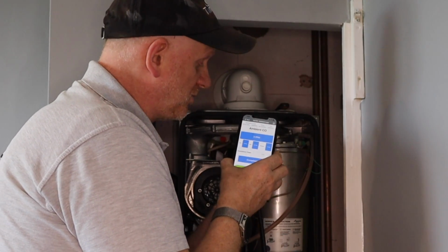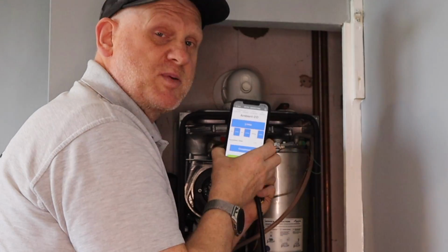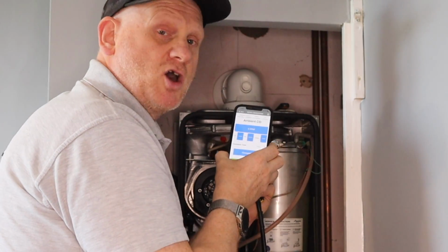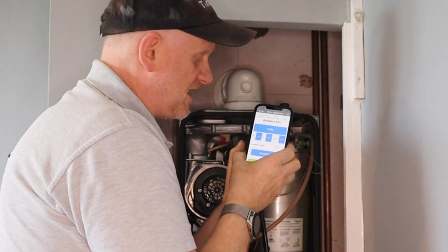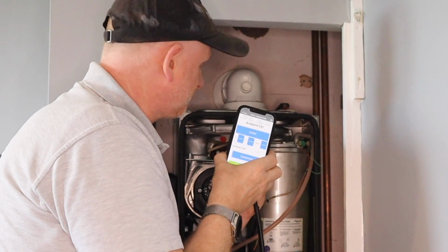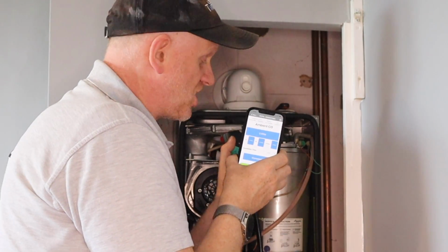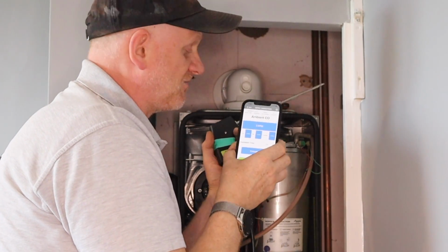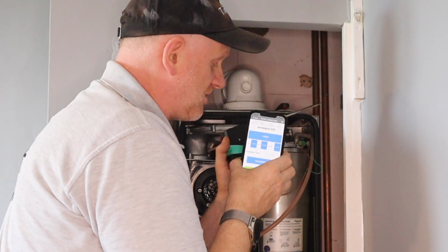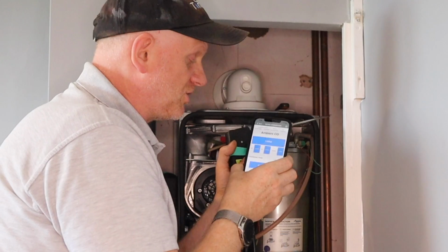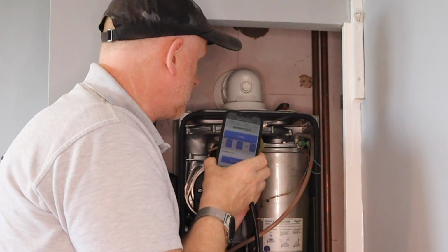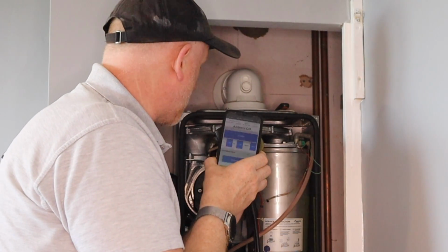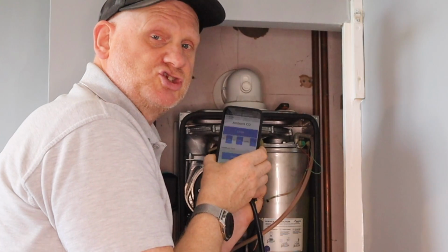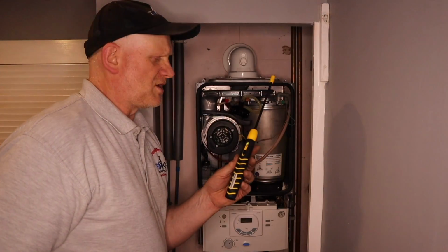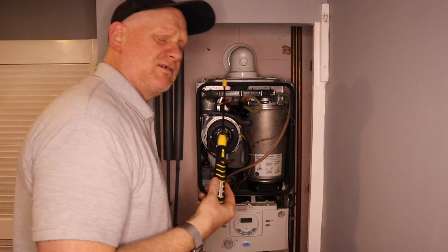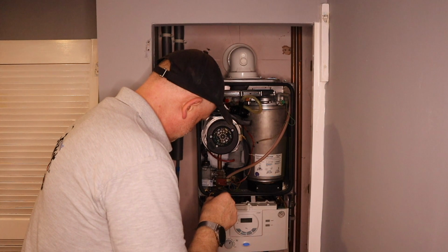So the test is complete and I got 3 parts per million of CO inside there, which isn't anything for concern, I wouldn't have thought. It's obviously going down now because I've pulled this down. So that's the maximum we got, which was 3 parts per million of CO coming from the top of this combustion chamber. I'm also going to use my Kane gas sniffer to see if we've got any gas leaks.